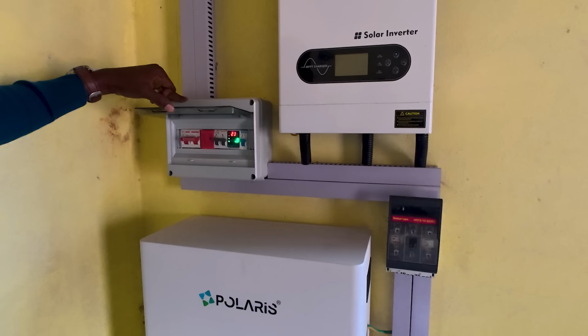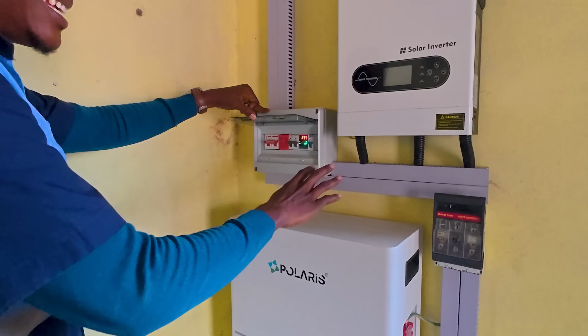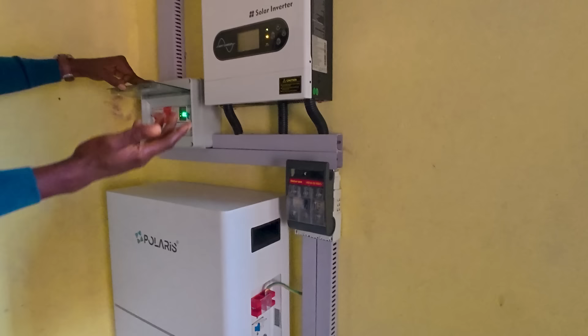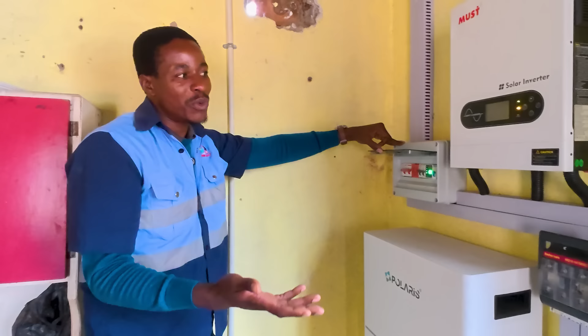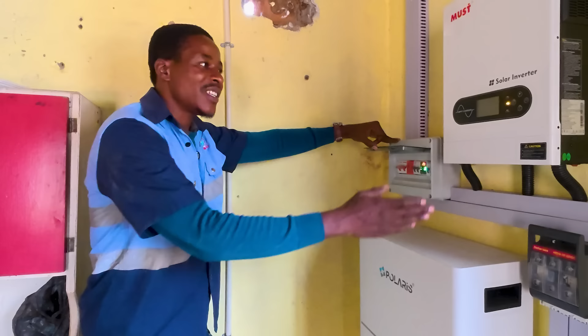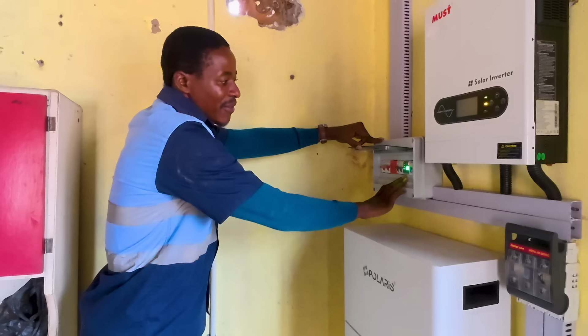Same with current, you can also set it here. For instance, if we don't need current more than 30 amps to come out from the solar system, we just set it to 31. So when the current surpasses 30 amps, the AVS cuts off the power supply. This protects our inverter from damage, like if you plug in a high consuming gadget such as a grinder or a welding machine that surpasses the current this inverter can generate, the AVS will just stop at that set current or voltage.